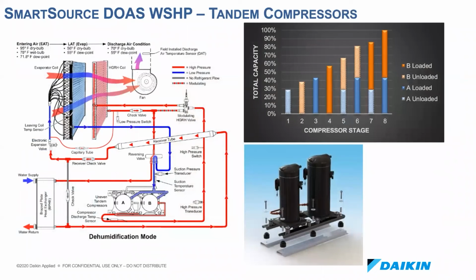So the compressor tandem consists of 2-stage scroll compressors that are mounted on common rails and piped together into a single circuit. The compressors are not the same capacity. For example, a 10-ton tandem may have one 4-ton compressor and one 6-ton compressor. With these uneven capacity levels, the different combinations of being on or off, operating at loaded or unloaded, result in 8 steps of capacity control as shown in the graph. The minimum capacity level varies a little bit between the different size tandems, but it's typically around 30%.